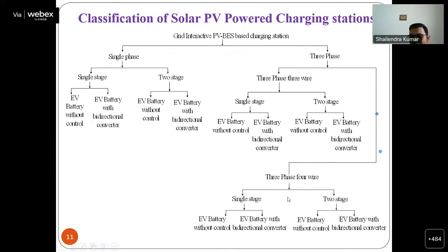In case of a three-phase, four-wire charging station, we have to use an extra leg for the voltage source converter. When we charge our vehicle, neutral currents keep tracking, and this fourth leg is utilized to mitigate this grid neutral current.